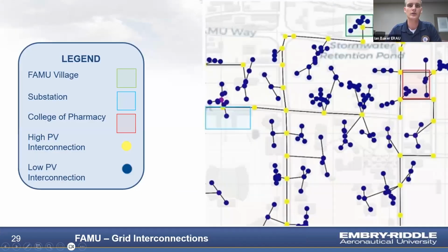In our design, only two buildings pose a threat to the stability of the grid. The loads of the College of Pharmacy and FAMU Village were large and inconsistent. We determined the grid can easily handle the loads with a PV capacity of 4,200 kilowatts for each yellow interconnection point on the heat map provided for the district. The largest system for the College of Pharmacy totals only 580 kilowatts. The smart inverter chosen monitors the building's varying loads and can take actions to prevent abnormalities in the grid.